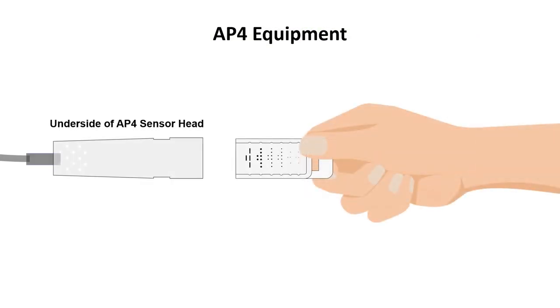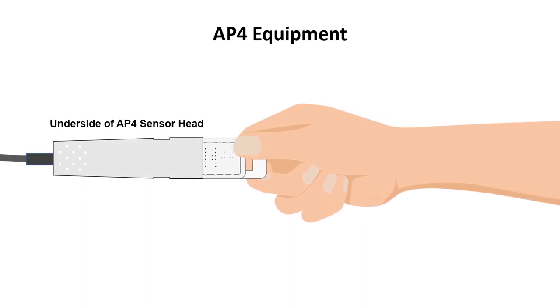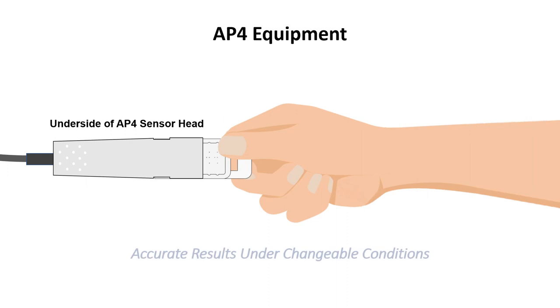The AP4 system also includes a calibration reference plate which inserts into the sensor head. This enables rapid six-point field calibration, ensuring consistent and accurate results under changeable conditions.